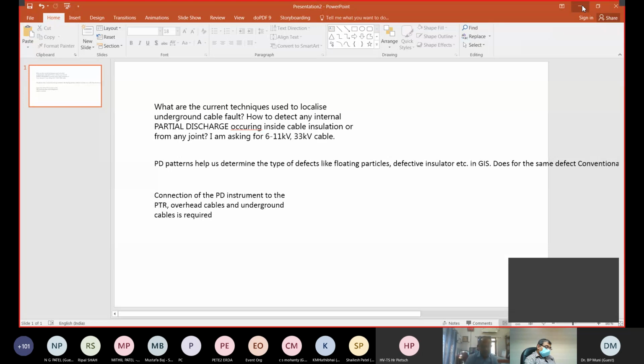If you just test with U naught as a normal stress, you will not detect the defect in a given time - definitely not in 24 hours, only if it's a very harmful or dangerous defect. Other defects need time, more than 24 hours. With higher stressed voltage, at 1.45 or even 2 times depending on the rated voltage, you need, by convention, 1 hour, and then you can pick up at least 80 or 90% of the possible defects introduced during installation or in cable joints. That's a question of statistics plus amplitude. So 24 hours is definitely not enough - only acceptable if you have no test equipment. But that doesn't mean you can be sure if you do this test. Be careful.